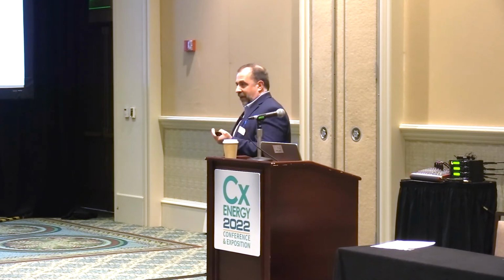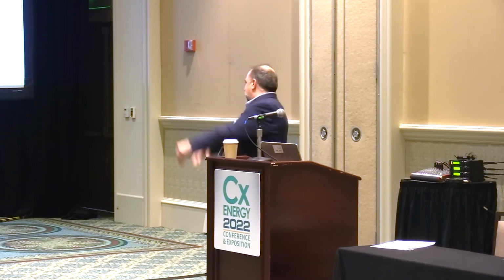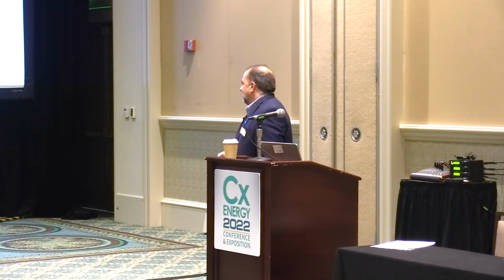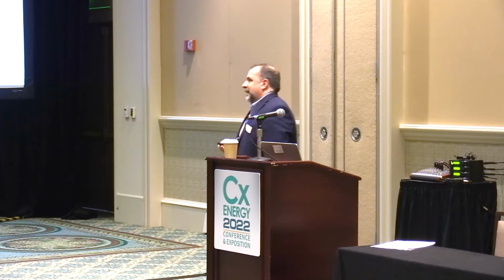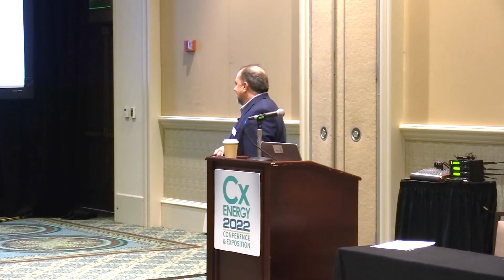But if I can't figure it out, even though I have access to the drawings and I'm familiar with the job, what are the chances the operations staff will know which fuel is spilling out in the generator room and what to shut off during an emergency? They're probably going to have trouble too, because we test when everything's calm, but that's not when problems happen—there's chaos involved. So I like to test to the chaos. If I can figure it out, then you're good.